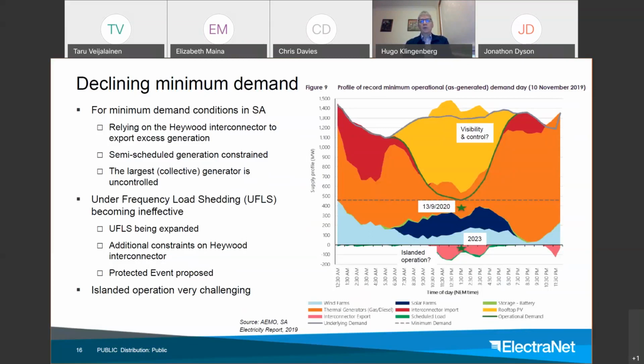More recently, in a review of under-frequency load shedding, which has been relied on for decades for emergency response to restore supply and demand balance under critical conditions, we've found it's becoming ineffective, to the extent that AEMO is shortly going to introduce an additional constraint on the Heywood interconnector to manage that. Also, between ElectraNet and SA Power Networks, the distribution company in South Australia, we're expanding the UFLS reach into customers that previously were deemed either too sensitive or too critical. So in a way, no load is off limits anymore for under-frequency load shedding.